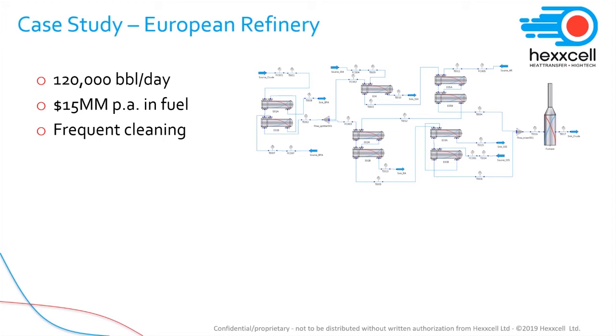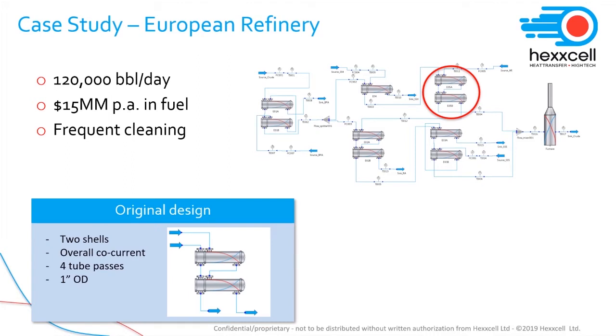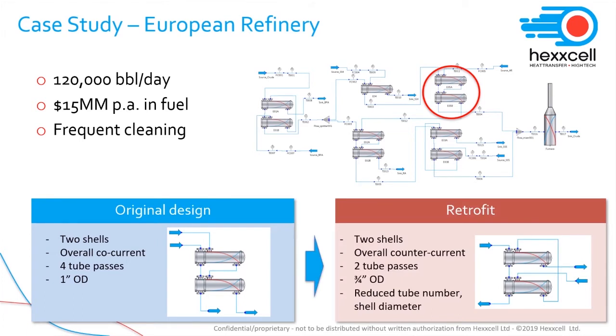So let me show you a case study for a European refinery where we studied a retrofit option. This is a 120,000 barrels a day refinery where we identify E05 as a potential candidate for retrofit. This is a shell-and-tube heat exchanger with a 2-shell, 4-tube pass, 1-inch diameter tubes. And we propose to reduce the number of passes to 2, but change the outer diameter of the tubes to 3/4 of an inch. We also reduce the number of tubes and the shell diameter. So to answer the question, how will this new geometry perform, we first go back in time and assess how it would have performed had it been in place 4 years ago, when operation restarted after a major turnaround. This approach allows us to estimate the trade-offs between capital and operating cost, return on investment, the ROI, using actual data from the specific plant, not generic assumptions that may or may not be applicable to that specific plant.